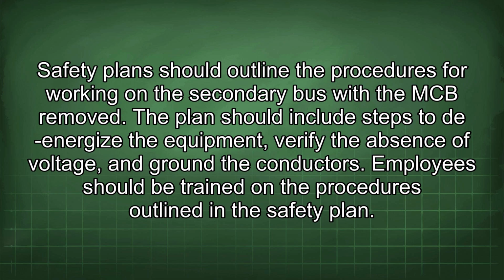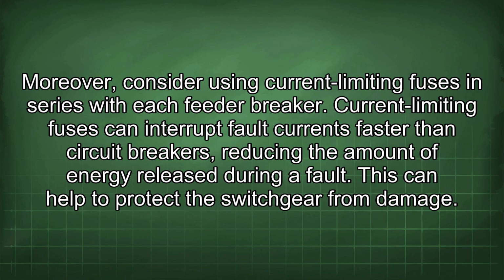Safety plans should outline the procedures for working on the secondary bus with the MCB removed. The plan should include steps to de-energize the equipment, verify the absence of voltage, and ground the conductors. Employees should be trained on the procedures outlined in the safety plan. Moreover, consider using current limiting fuses in series with each feeder breaker. Current limiting fuses can interrupt fault currents faster than circuit breakers, reducing the amount of energy released during a fault. This can help to protect the switchgear from damage.